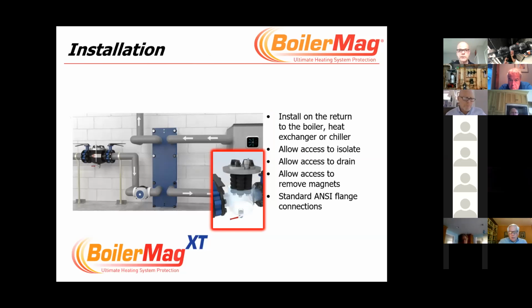I've got some pictures, hopefully, in the next couple of slides. This shows you how it's installed. Make sure you've got enough space above to pull the magnets out, and enough space below to drain it, giving yourself room to put some valves before and after it. This shows a simple system installed before the pump, before the heat exchanger, before the boiler. But like I said earlier, install it wherever is most appropriate, wherever you've got access to it, closest to the expensive piece of equipment you're trying to protect.